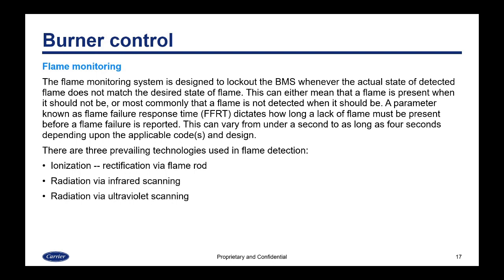The flame monitoring system is designed to lock out the BMS whenever the actual state of detected flame does not match the desired state of flame. This can mean that the flame is present when it should not be, or most commonly that a flame is not detected when it should be. A parameter known as flame failure response time dictates how long a lack of flame must be present before a flame failure is reported, and this can vary from under a second to as long as four seconds depending upon the applicable code and design.